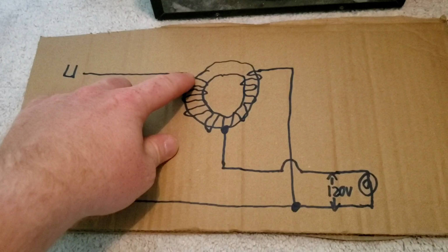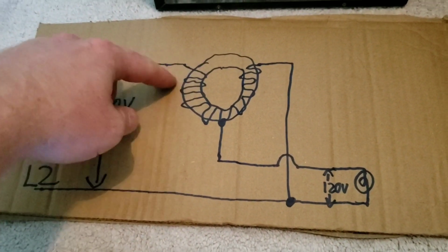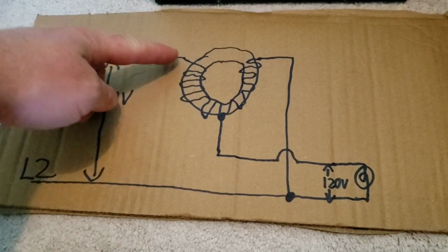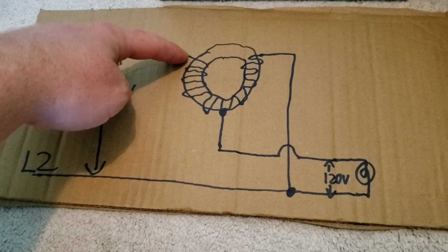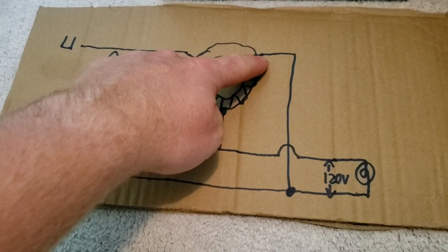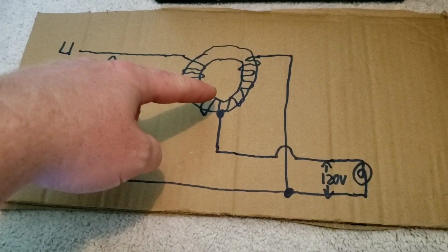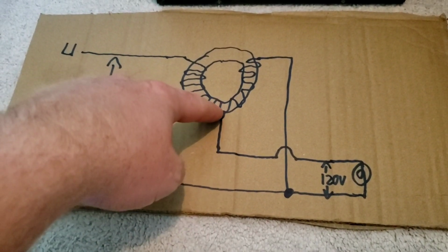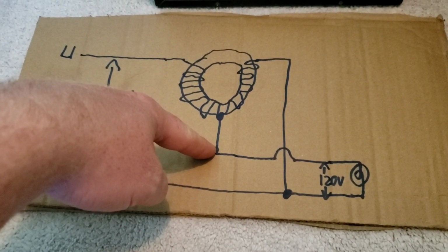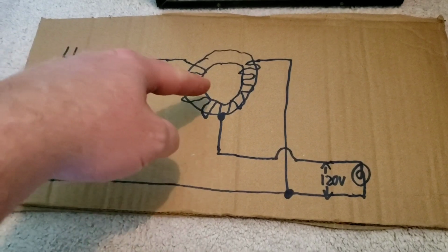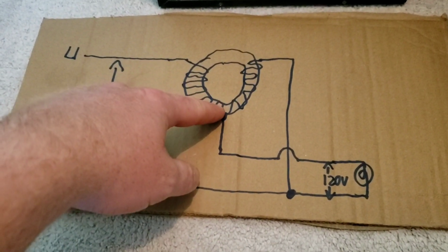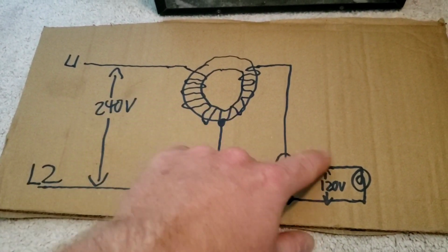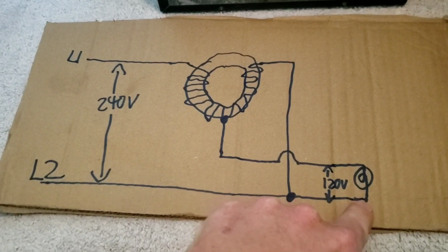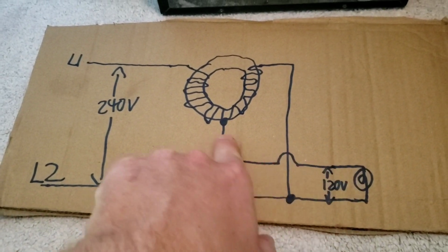So this is the transformer, and this is the winding that's supposed to go all the way around. You have one hot going to one winding, the other hot going to the other end of the winding - that's to feed the transformer. To grab, say, 120 volts, you have to grab the neutral - or this isn't really a neutral because it's not even grounded, so it can't be called a neutral. But basically you just have 120 volts between one of the hot conductors and that center tap.